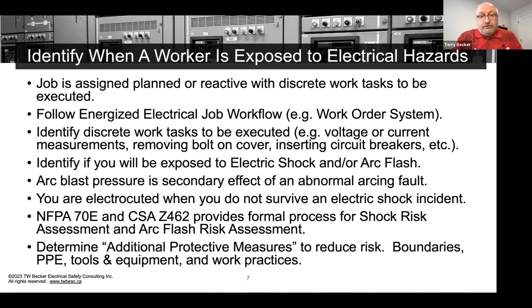All right. So identify when you're exposed. I've got a note there that arc blast pressure, I'll talk about that briefly, has been perceived to be extremely high pressure. That's also not true. So that continues to be communicated by me and others, but we also see some improved information generically coming to industry that arc blast pressure is not going to be extremely high in most cases. And again, if you're electrocuted, you didn't survive the electric shock. And we'll talk about, again, the unique shock risk assessment and arc flash risk assessment procedures that are in NFPA 70E and Z462 to determine additional protective measures, which is the PPE, tools and equipment you need, and the boundaries. So the shock protection approach boundaries, the arc flash boundary, and other practices and procedural requirements you'll need to use, again, to reduce risk.